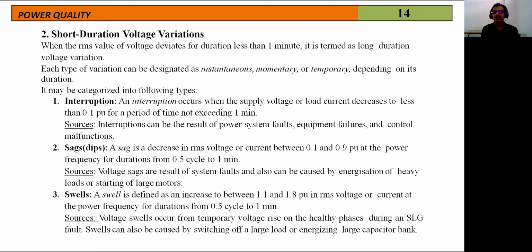Okay, when we call it an interruption, it means the supply voltage or load current decreases to a very small value, less than 0.1, so it decreases almost to 0. When the voltage or current suddenly drops to a very low value, less than 0.1 pu, that means less than 10%, that is known as interruption.